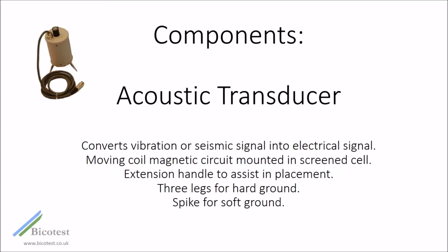The acoustic transducer converts the vibration or seismic disturbance created at the fault into an electrical signal. The transducer comprises a moving coil mounted in a magnetic circuit contained in an inner screened case to eliminate pickup from any external electromagnetic interference. A waterproof outer housing also provides further efficient screening. An extension handle is provided which may be screwed onto the top of the case to facilitate moving and placing the transducer.